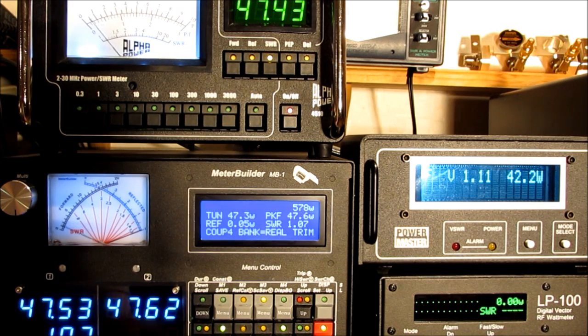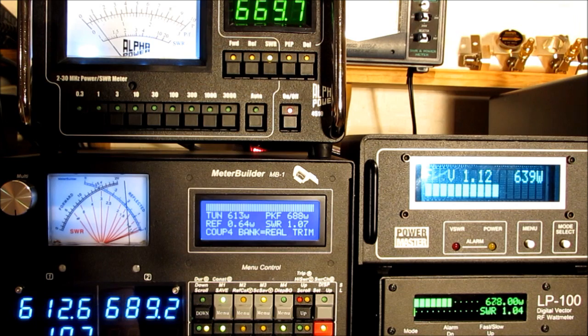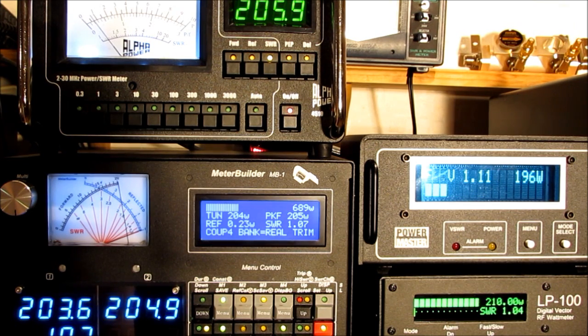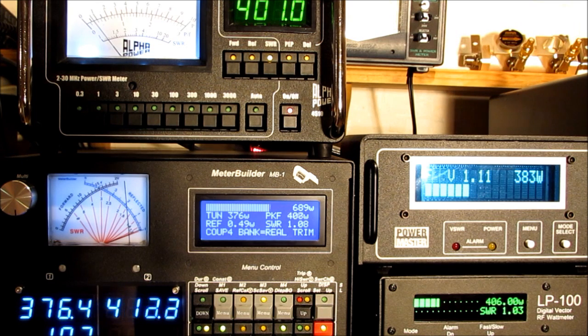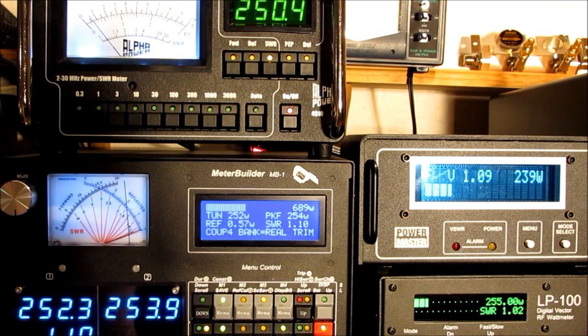Okay, now I've got to power up the amplifier. Remember, we calibrated this up to 500 watts. And actually the meter will measure above 500 watts, but because we don't have any calibration points above 500 watts, it's going to use the calibration point for 500 watts to figure out the calibration curve for any power above that. So the point is that you really want a calibration point at the highest power you intend to use.